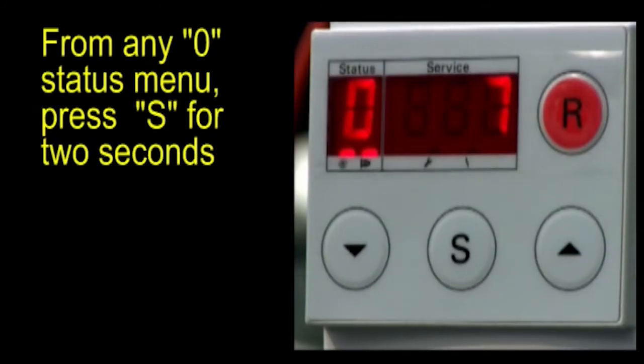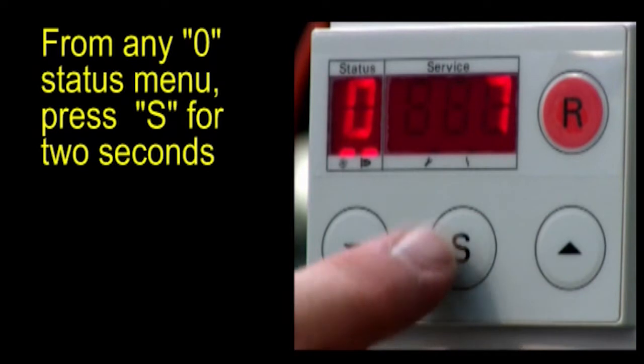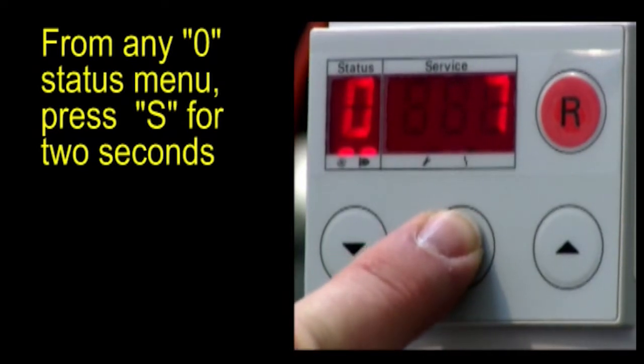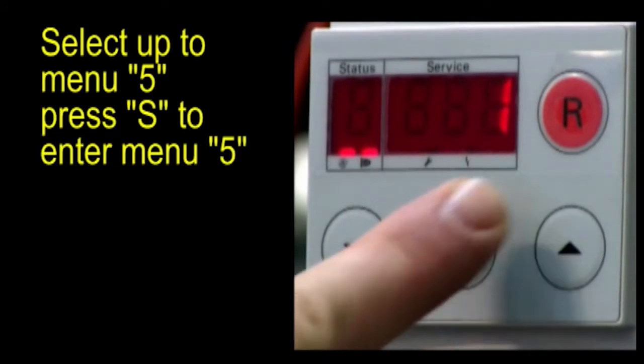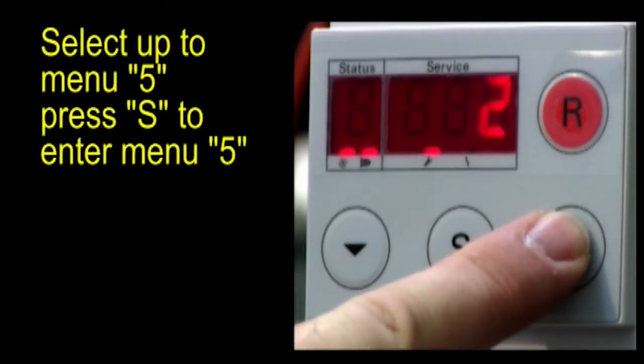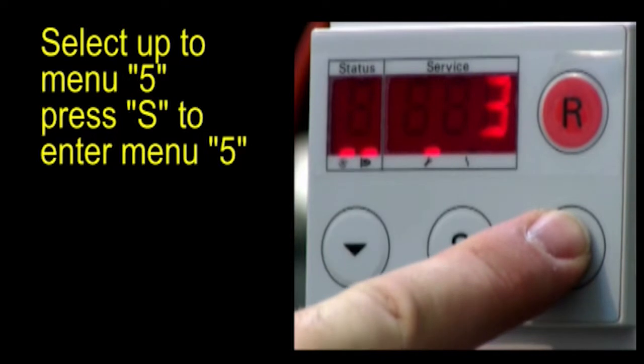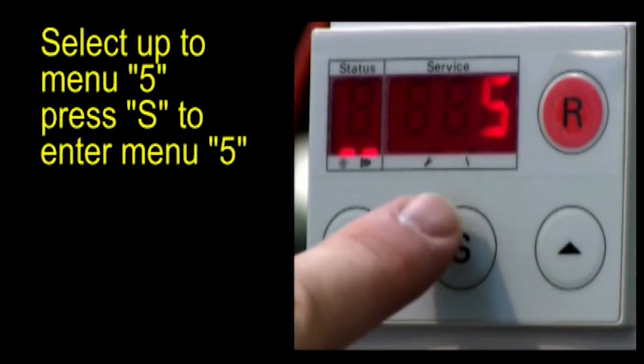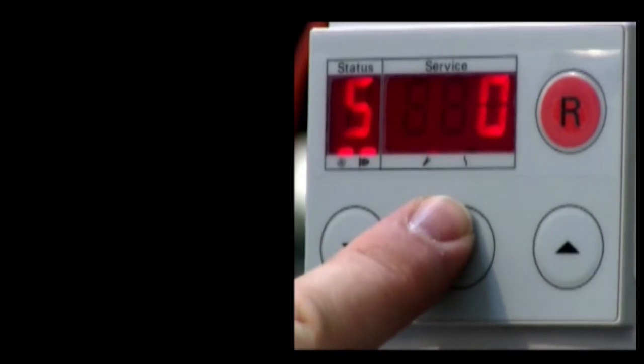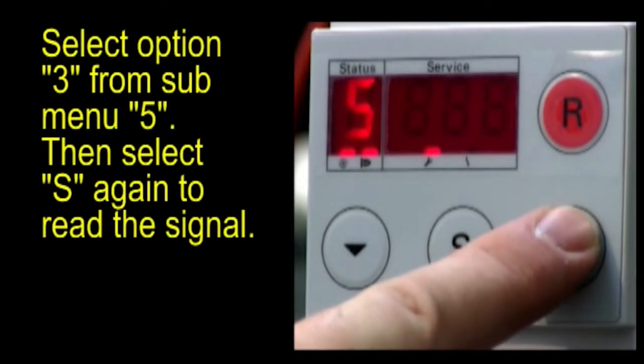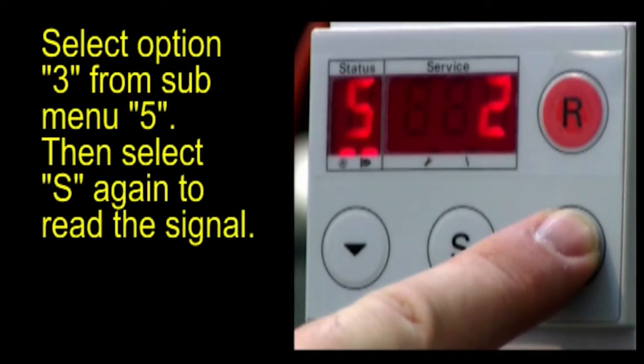From any zero status menu, press S for 2 seconds. Select up to menu 5, press S to enter menu 5. Select option 3 from submenu 5, then select S again to read the current flame signal.